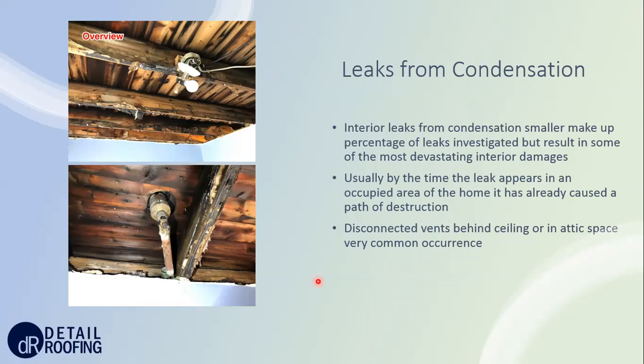One of the things that we see very commonly that leads to excessive condensation is disconnected vents behind the drywall ceiling or in attic spaces. So the hot air from these vents just blowing into these spaces and creating so much condensation that it leads to active leaks within the unit.